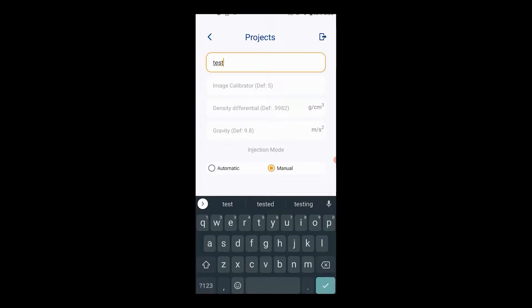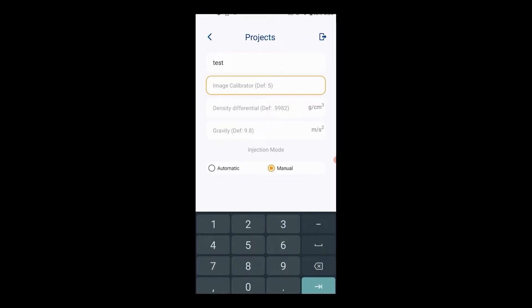We recommend that you measure the diameter of the needle with a micrometer before starting the experiment to ensure proper calibration. The differential density is the density difference between the liquid and its outer gas or liquid.